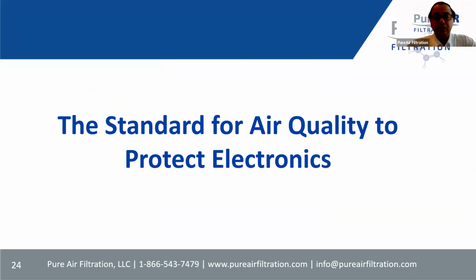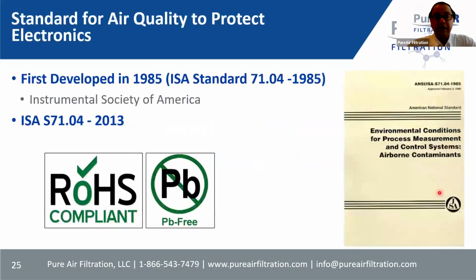So which standard do we follow to monitor the air quality and to protect the electronics? We have ISA 71.04, which was developed in 1985, and the latest version is ISA 71.04-2013. The purpose of the ISA standard is to classify airborne contaminants that may affect process measurement and control instruments. There are a lot of companies like Honeywell, IBM, or Samsung that don't give any warranty on the equipment if the room is not properly maintained. It's the G1 classification. In a later slide, I will discuss the G1 classification, how it is classified, and that it should be RoHS compliant.